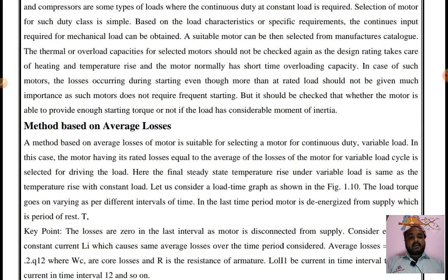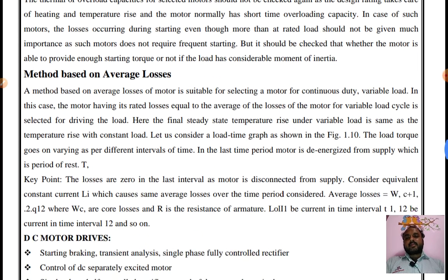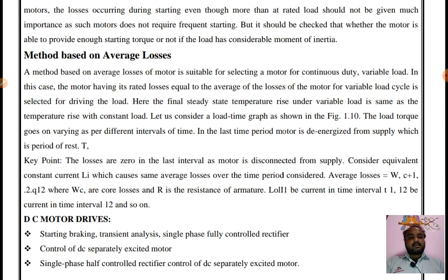In case of such motors, the losses occurring during starting, even though more than the rated load, should not be given much importance, as such motors do not require frequent starting. But it should be checked whether the motor is able to provide enough starting torque or not, if the load has considerable moment of inertia.